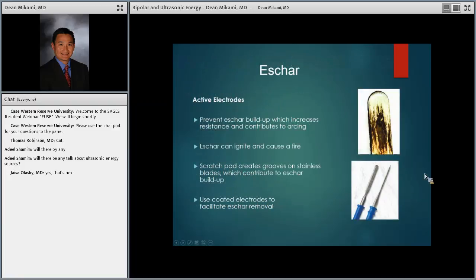One of the big things that we see a lot of is the eschar that forms on our instrument. You really want to prevent eschar buildup because it increases the resistance and contributes to arcing. The active electrode is sending current, giving you a tissue effect, going back to your return or your dispersive electrode. As that eschar builds up, the current has to go around it, so you won't get the effect right at the tip where you're working. If you have a lot of eschar, you'll get this big kind of ball effect of the energy going through that area that you're working on. The eschar can also ignite, causing a fire.